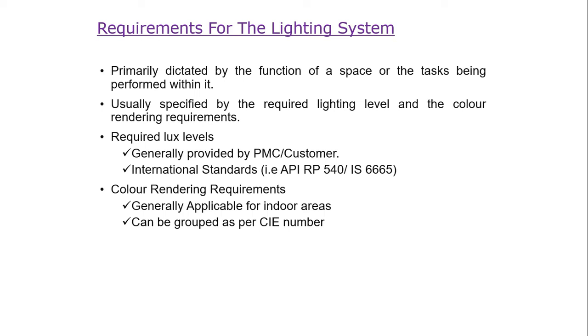There are two broad ways how lux levels are defined. If you are working for a particular client or customer, they have their own standard design or standard working procedure, and they can suggest their standard lux level that they would like to maintain in their process units or buildings. Otherwise, in absence of that, we can refer to international standards like API RP 540 and IS 6665, which give us the standard values or best engineering practice lux level values that we can utilize for a particular project.